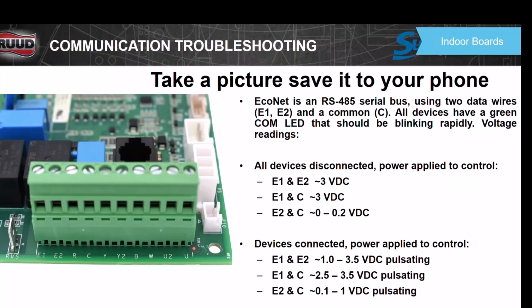If you go from E2 to common, you're going to have anywhere from 0 to 0.2 volts DC. That's your communication happening. If you don't have a fluctuation, or you don't have the voltage here, you've got a bad communication wire between this component and wherever it's at. So go to the next component.